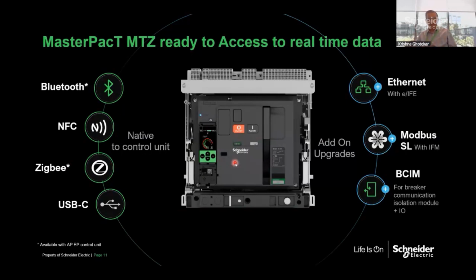No, we will also have our legacy accessories which we use, like IFM, Modbus module, or IFE, Ethernet module, IO, and so on. So all those modules also will be there for MTZ Active modules. But again, those are add-on. This one, what we are talking about, wireless communication, is native to the electronic trip unit, and it can seamlessly connect to PAS gateway. So this is, in terms of BOQ optimization, in terms of integration, in terms of doing the panel connections, much more efficient. Having said that, legacy accessories are also there.